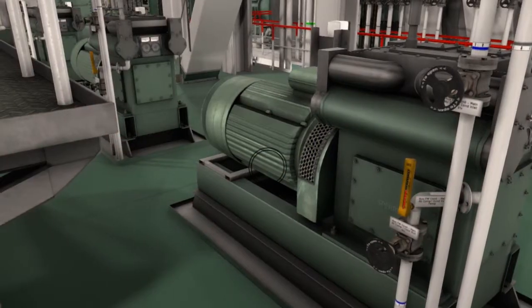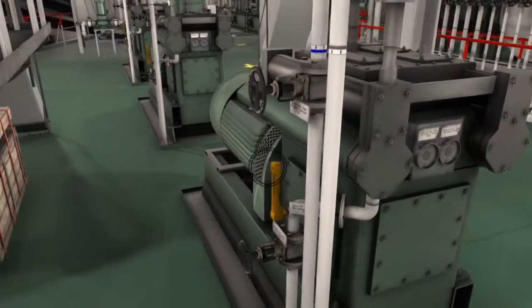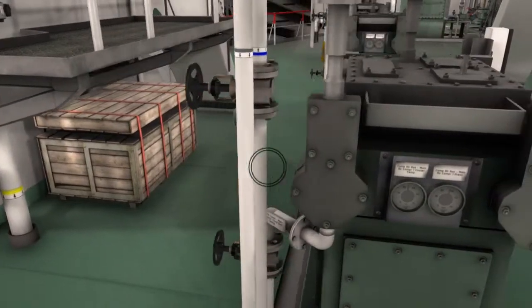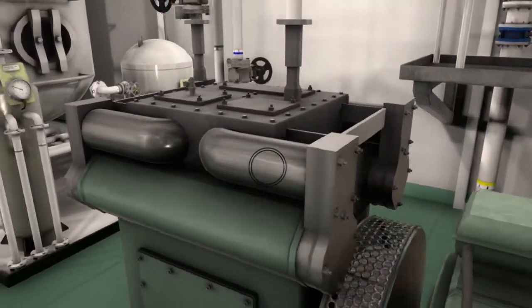Now let's look into the air compressors. These are air cooled and provided with an unloading gear, a safety valve after compression stage, and a non-return valve on each compressor discharge. Each vessel is provided with a safety valve set 10% above the operating pressure.